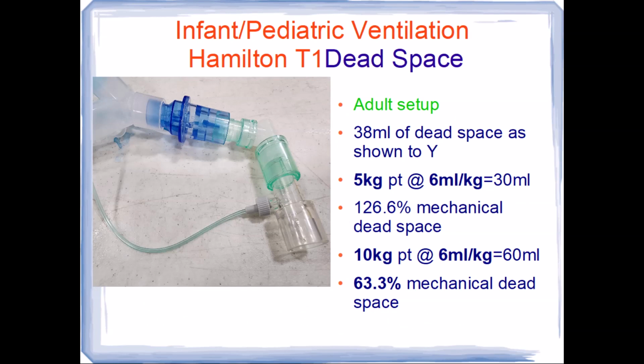So this is our adult setup. So from the beginning of the end tidal CO2 connector up through that swivel adapter, and notice this is not the swivel adapter with the corrugated tubing or the slinky adapter. This is just the standard swivel to the flow sensor and up to the Y. We have 38 milliliters of dead space. So from the very beginning up to the Y, where it goes down through the corrugated tubing and makes its way to the expiratory valve.